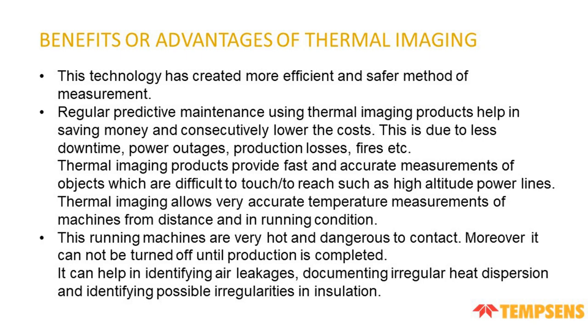Thermal imaging products provide fast and accurate measurement of objects which are difficult to reach or touch, such as high altitude power lines. Thermal imaging allows very accurate temperature measurement of a machine from a distance in its running condition. Running machines are very hot or dangerous to contact, and moreover cannot be turned off until production is complete. It can help to identify air leakage, document irregular heat dispersion or identify possible irregularities in insulation.